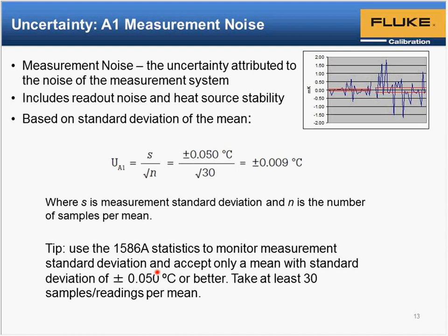The 1586A has statistics built in to calculate the mean and standard deviation. And I believe it even has a built-in calibration program that will communicate with the furnace. I think it's built to communicate with at least some of the Fluke temperature equipment. It will control the furnace to move to different set points and take data at each set point. So that helps, so you don't have to use Excel or something to calculate measurement standard deviation. This applies to both the reference probe and the UUT probe.